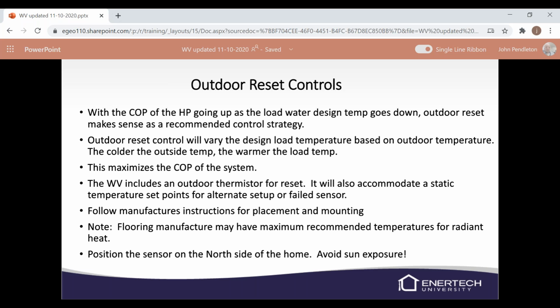Again, the thermistor is included with the unit. And if for some reason it fails or is broken or you can't get it installed, there is a static set point in the HMI for a failed sensor. Make sure we're normally positioning that sensor on the north side of the home and that we're avoiding sun exposure. That'll cause it to give a wrong temperature reading.